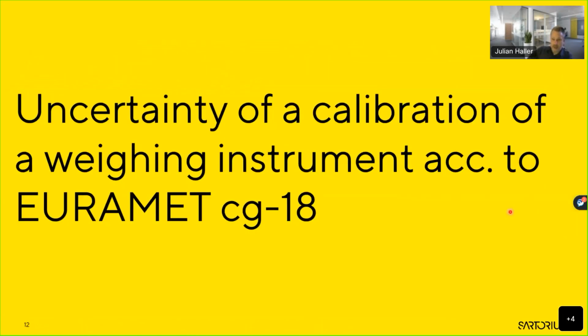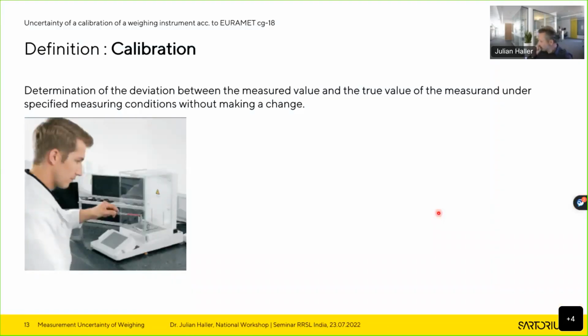Actually, it's a long document, and I would just like to give you a short overview of how the uncertainty of a calibration of a weighing instrument is determined according to this document. Now, sorry, let's start with the definition of a calibration. The calibration is the determination of the deviation between the measured value and the true value.